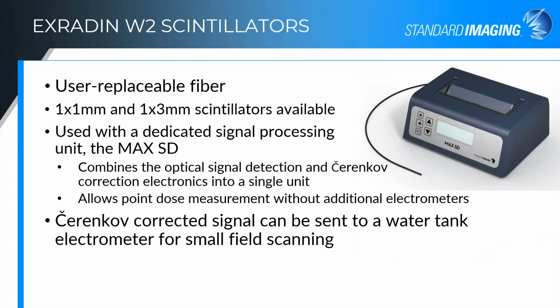The W2 was our second generation device then, based on what we learned with the W1 as well as feedback from users of the W1. We were able to combine the optics along with the signal processing electronics into a dedicated electrometer, which we call the Max SD for scintillation dosimetry. The fiber then is just the fiber, the W2 fibers. It doesn't have those optics on the end like the W1 does. So this has just a standard optical plug on it. So the fiber can be replaced by the user.